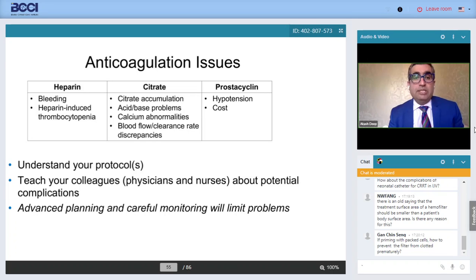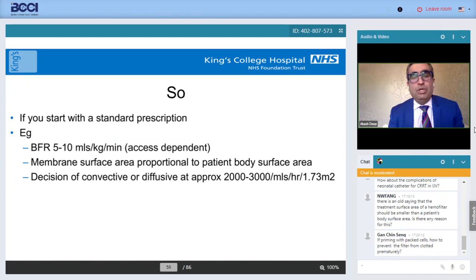So this is just a summary of your anticoagulation. Please make sure you understand your protocol. The nursing staff, the physicians and nurses should know about the potential complications. And again, advanced planning and careful monitoring will help limit the problems. So if you start with a standard prescription, a blood flow rate which is at least 50 mils per minute for a newborn, and you can go up based on the weight and the size of the patient. Choose a membrane surface area proportional to the patient's surface area. Decide you're going to give convection, diffusion, or a combination of the two at 2 to 3 liters per 1.73 meters square per hour. Again, depends upon your local policy.